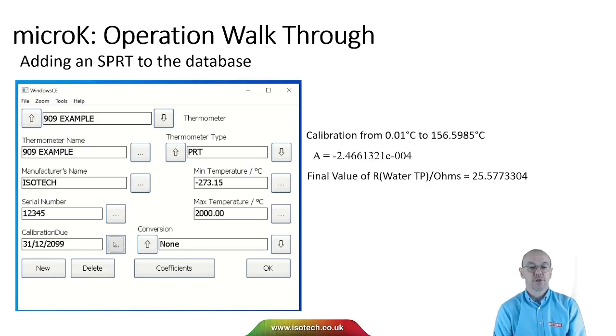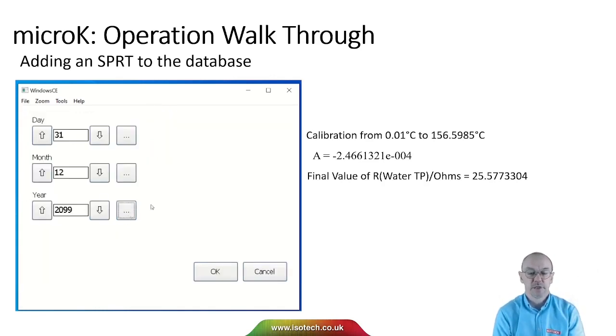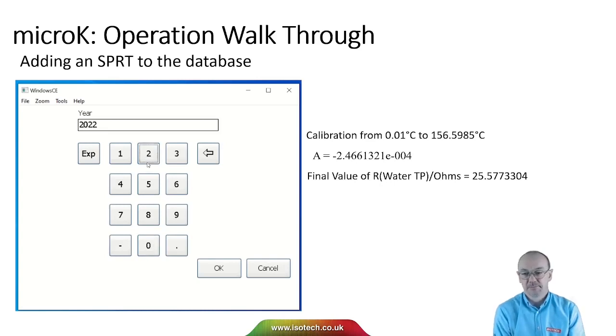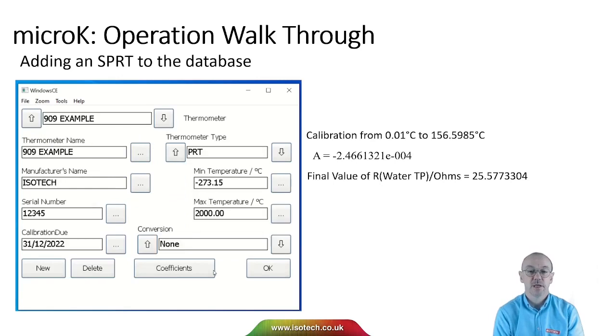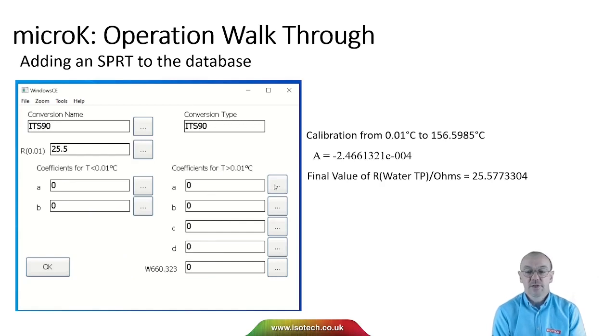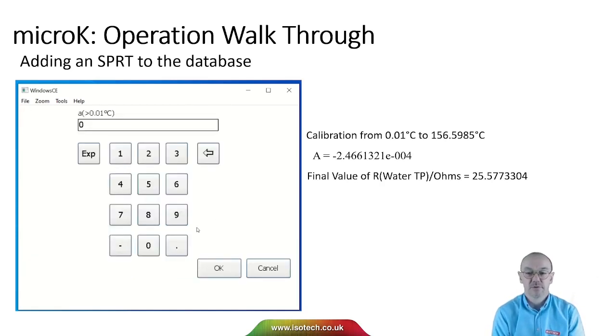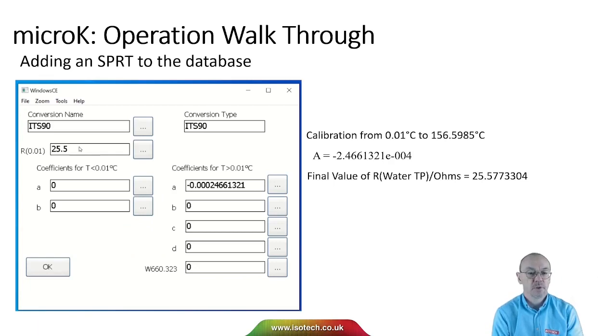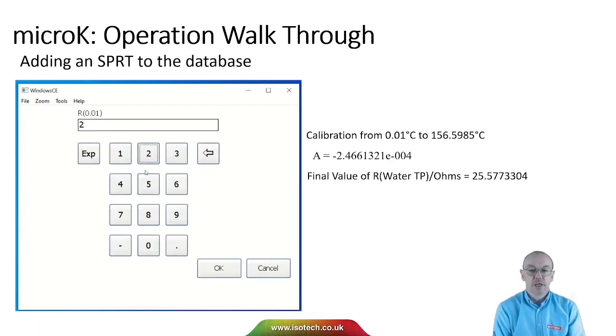If I put the calibration due date in, I can get the MicroK to tell me when the SPRT needs to be recalibrated. It doesn't affect the calculation, of course, but it's good housekeeping. I like to do that. Now for the conversion, I'll choose ITS 90, go for coefficients, and I just need to put the A value in here, which is from our calibration certificate. Once I've got that value in, I'll also put in the water triple point value. If I was using a wider temperature range, I'd have more coefficients to enter. As I said, in this example we just need the single one here, and then the resistance of the SPRT at the water triple point value.